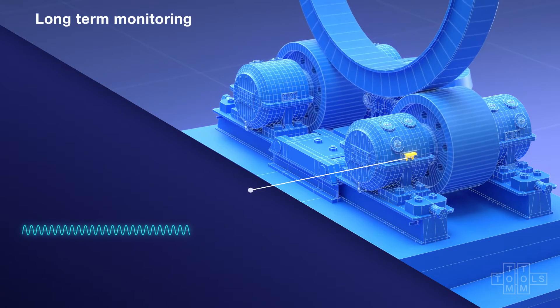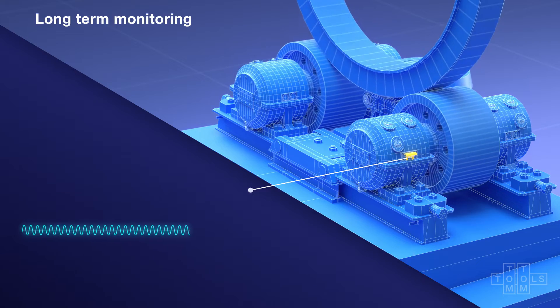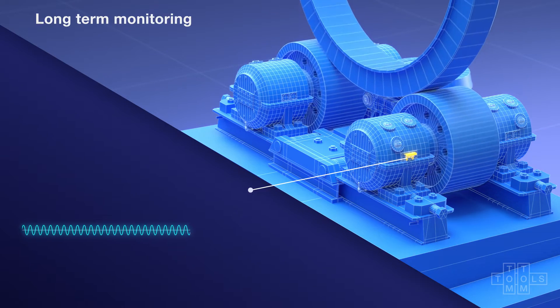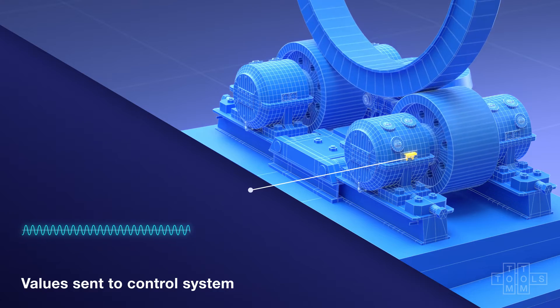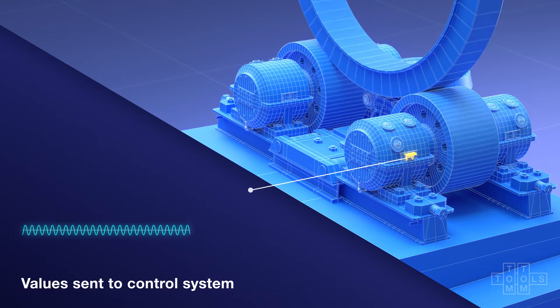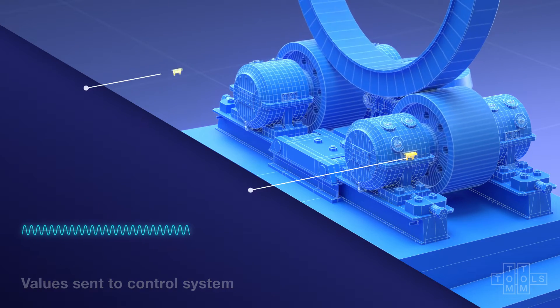This model is permanently installed, continuously measuring the tilting. The measured values are typically displayed and trended in the plant's control room, where alarms can be set to warn of potential roller overload.